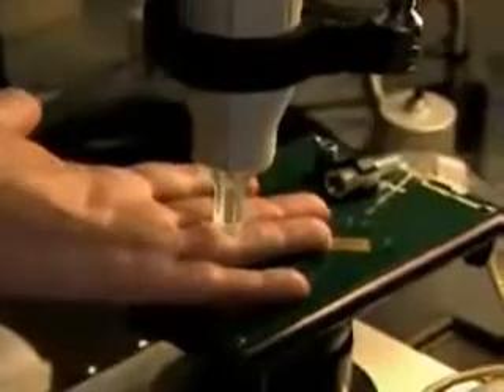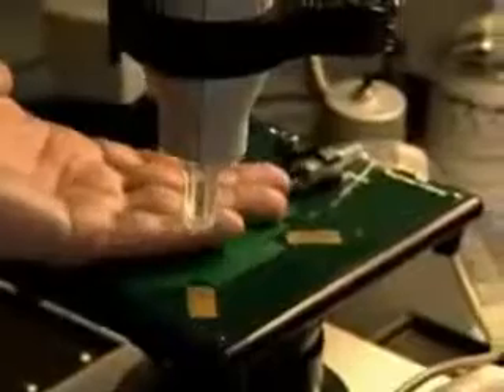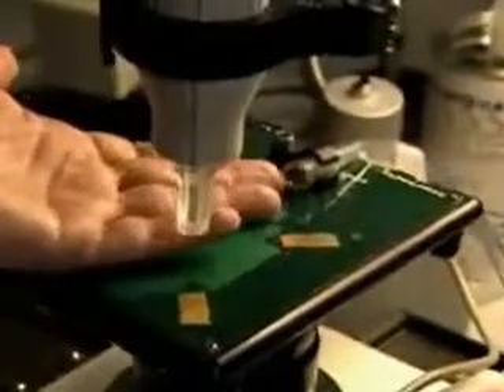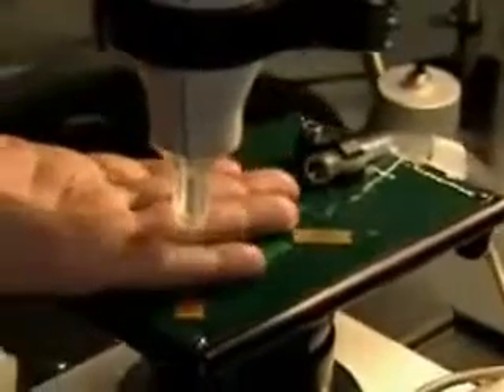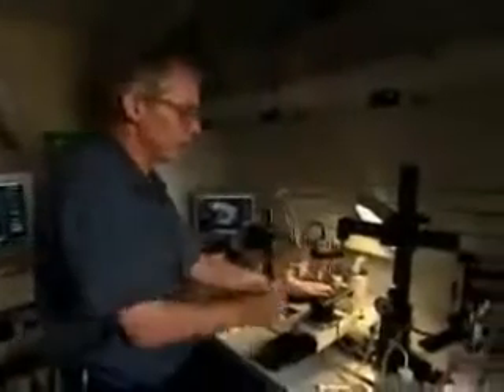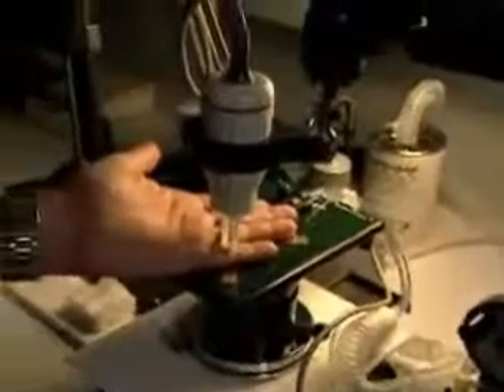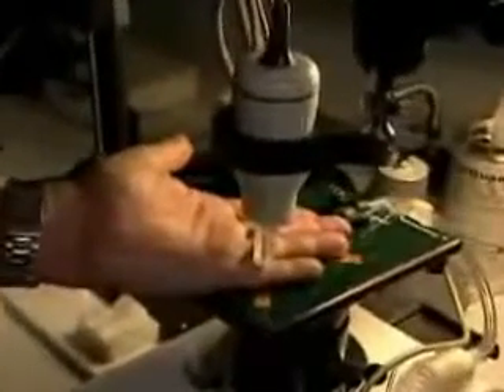Well, if I wanted to do a cardiac study on a mouse, I would take my mouse and place it on a comfortable stage here in which the paws are contacting these electrodes. That gives us an ECG monitor for the mouse. And then the mouse's nose goes in this little opening, and that's an anesthetic gas that keeps the mouse calm and comfortable. And when I want to image, I have my scan head here. I lower that scan head onto the mouse, or close to the mouse, through usually some kind of gel, and then we proceed with the imaging procedure.